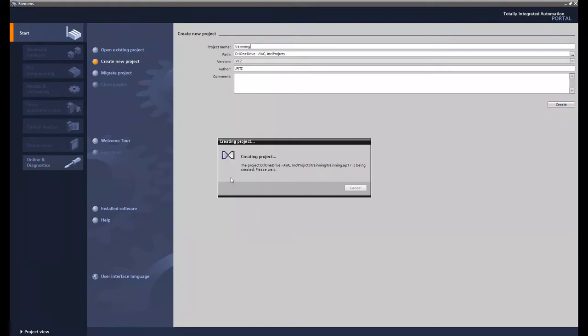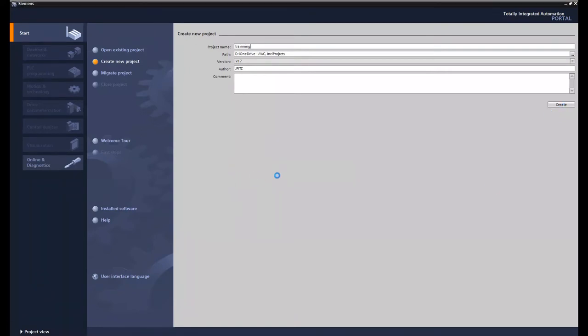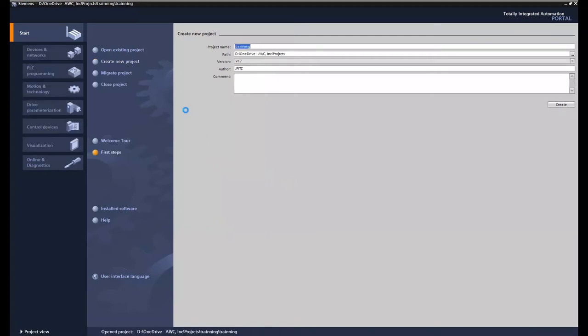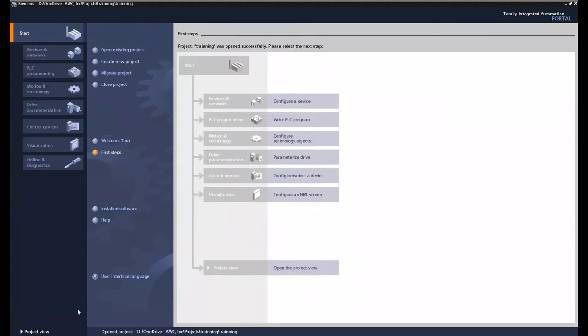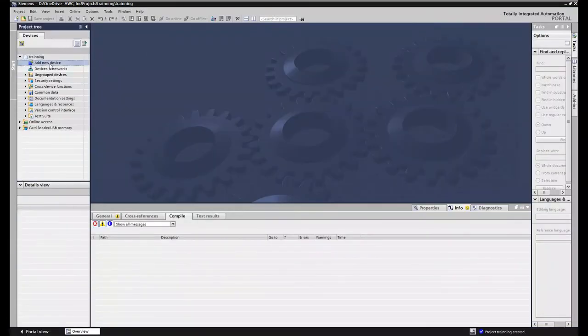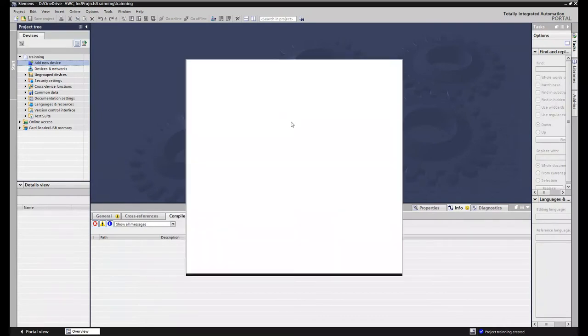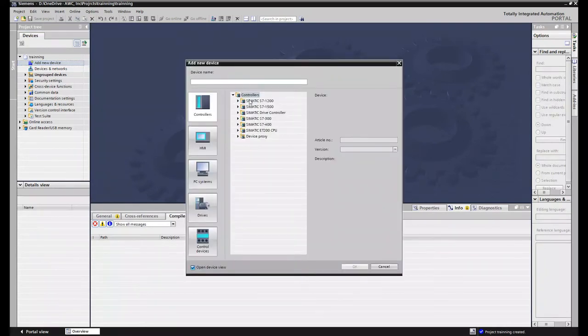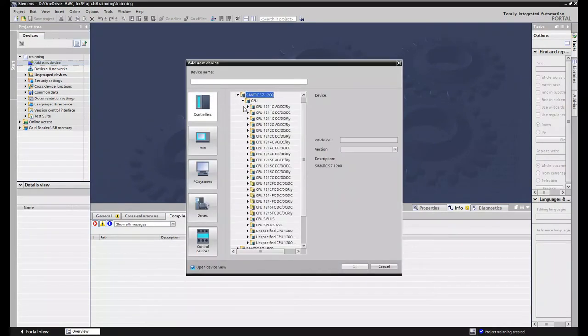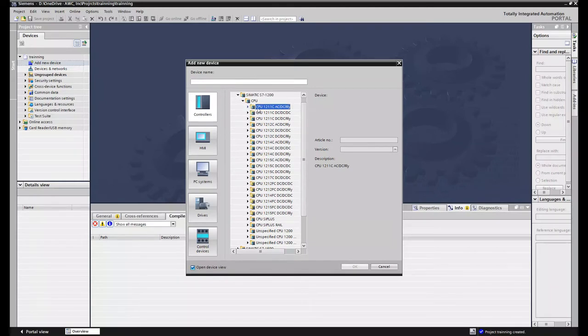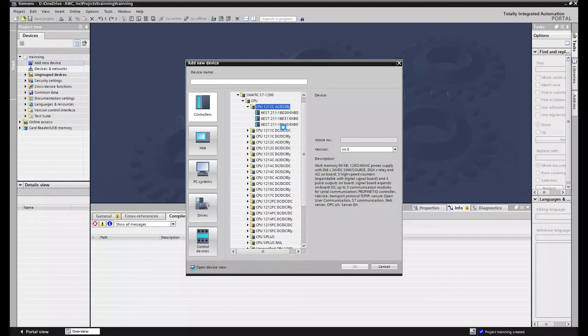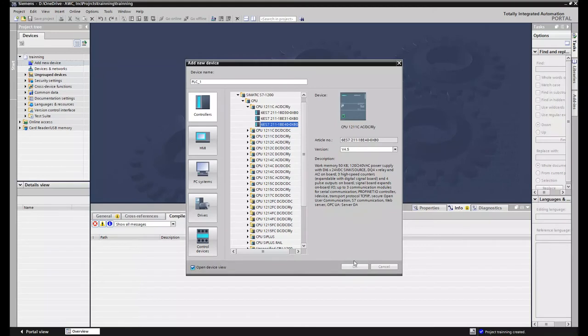Once we have our project open we're just going to add an S7-1200. I'll just put a fake one in there so I can use the simulator. So I'll just go to project view right here on the bottom left. Go to add new device in the project tree and choose our 1200. I'll just choose CPU then 1211 AC DC relay. Expand that out. And then I'll just grab the latest one which is 4.5. Save. Say OK.